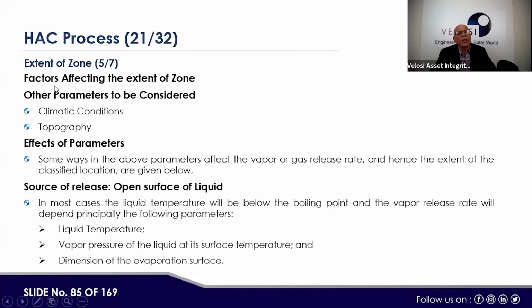Similarly, for the other parameters to be considered, climatic condition or topography, we look at the effect of the parameters. Some ways in which the above parameters affect the vapor or gas release rate, and hence the extent of the classified locations, are like this. Take liquid temperature, for example, where the source of release is an open surface of liquid. In most cases, the liquid temperature will be below the boiling point, and the vapor release rate will depend principally on the following: liquid temperature, vapor pressure of the liquid at the surface temperature, and dimension of the evaporation surface.